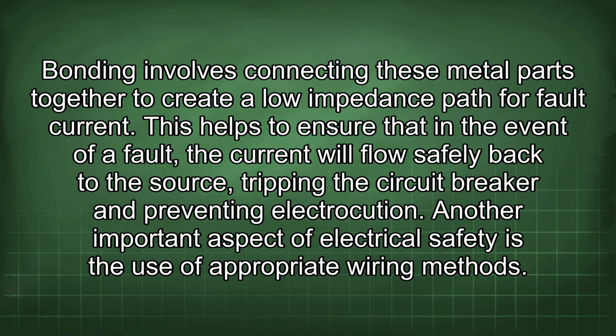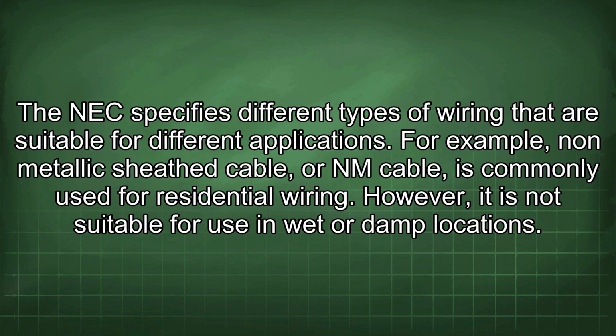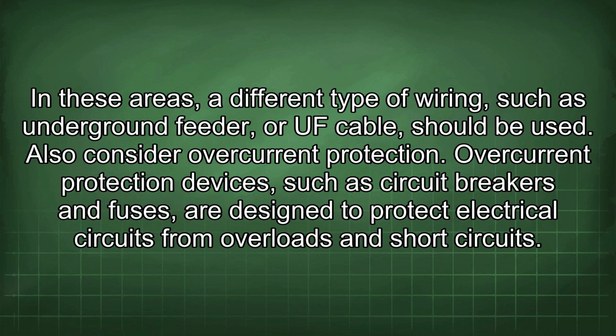Another important aspect of electrical safety is the use of appropriate wiring methods. The NEC specifies different types of wiring that are suitable for different applications. For example, non-metallic sheath cable or NM cable is commonly used for residential wiring. However, it is not suitable for use in wet or damp locations. In these areas, a different type of wiring, such as underground feeder or UF cable, should be used.